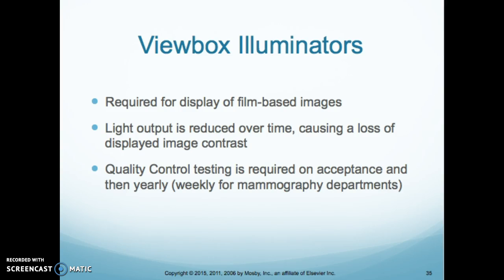The light output on these view boxes reduces over time, and what happens with that, it reduces our image contrast. When we're actually doing a diagnostic image that a radiologist is going to read, there's QC that has to happen, and we need to make sure that the view boxes are up within code. There's quality control testing on these view boxes when we accept them from the vendor, and then yearly after that, and when we're working in mammography, they're done weekly.